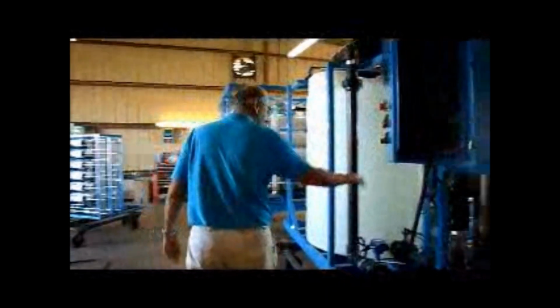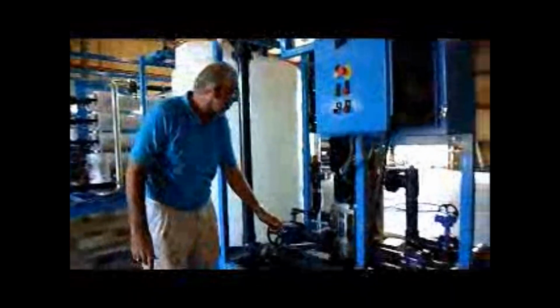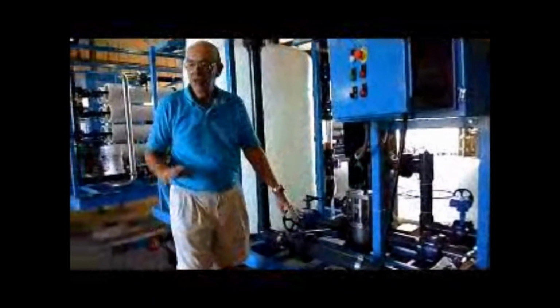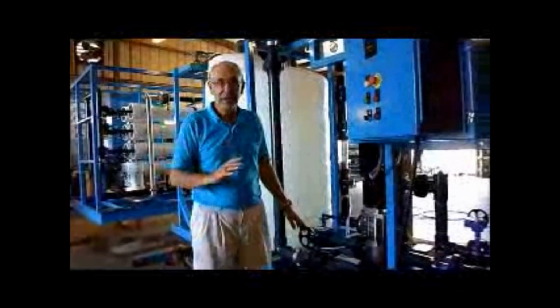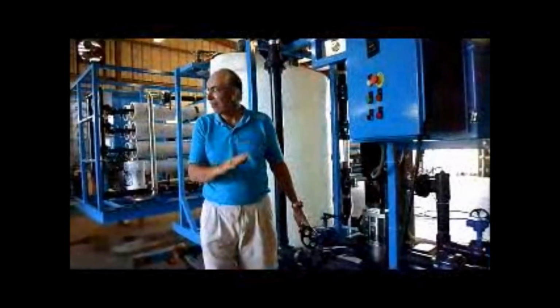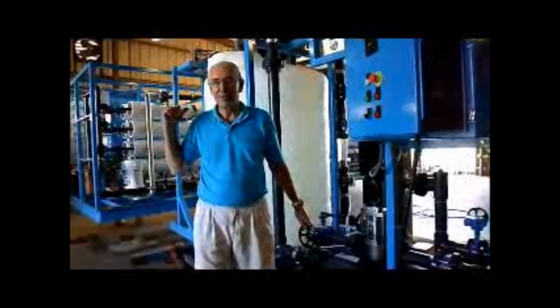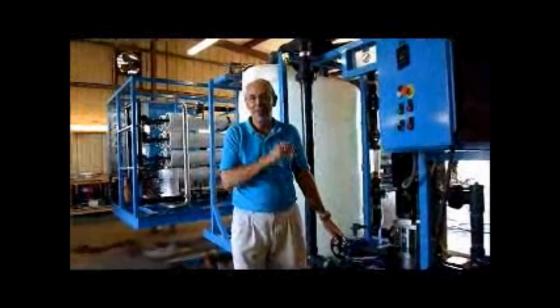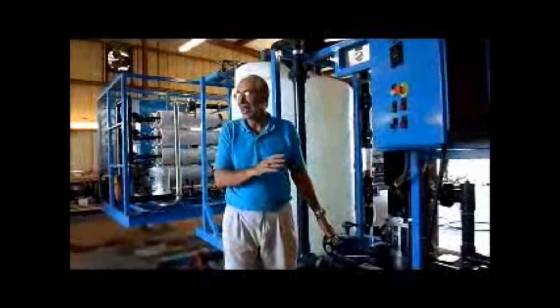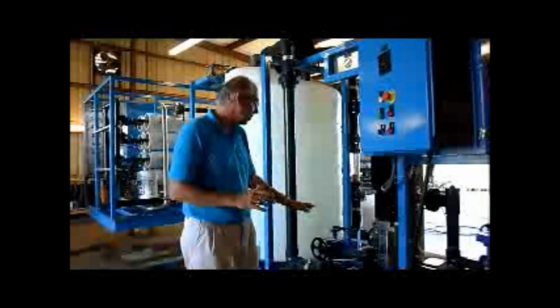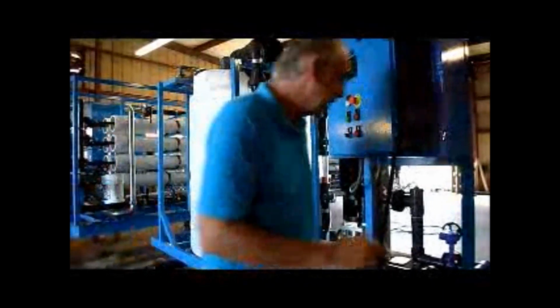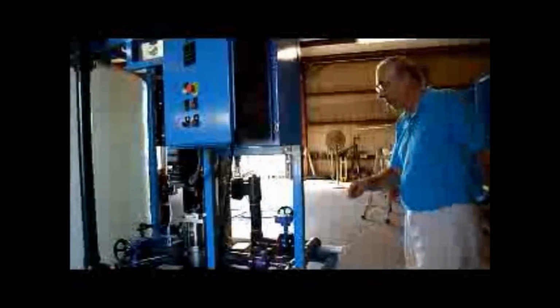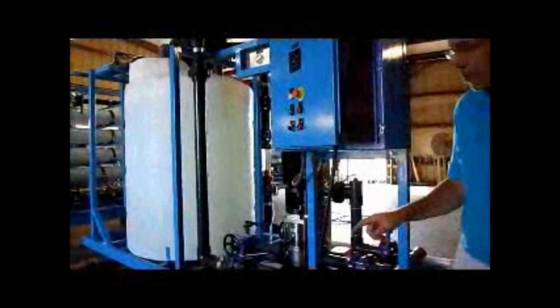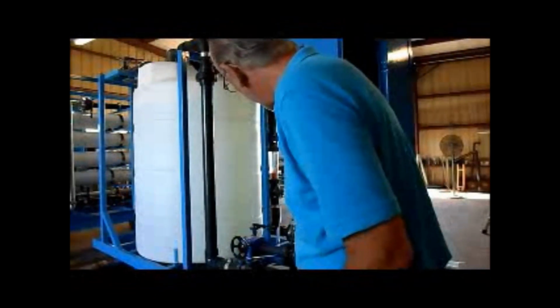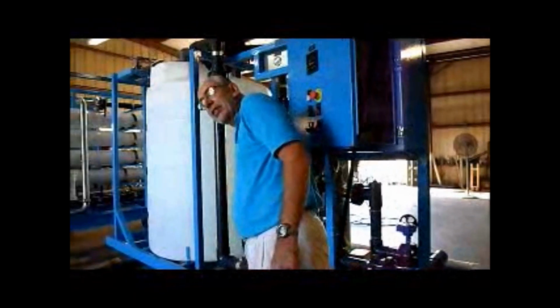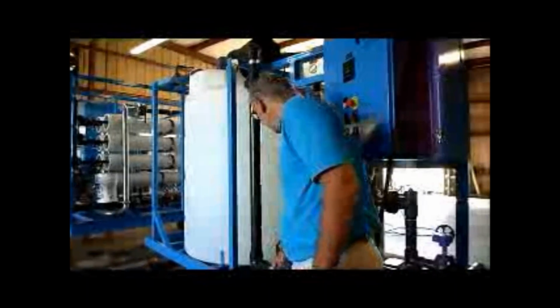If you can't get enough flow over there, you can start to close this valve and then the flow will go up. But I would do all that first with permeate, not chemicals. After you have everything the way you want, then run chemicals. It's a lot easier to fix a leak if you have water, not nasty hazardous chemicals. So the first step, open that completely, close this completely, run the system, circulate for a while, then close, open that valve, and then if necessary, close this one off.